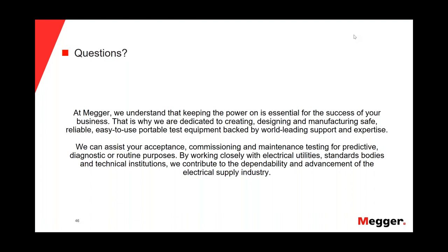All right, thank you. Henning, what is the difference with measuring PD in millivolts instead of picocoulombs? Well, I think that question depends a little bit on which method you're using. If you use a conventional method, you're typically using the PD in picocoulombs. And if you use an unconventional method, then you use millivolts. But if you use the typical standardized method, which follows IEC 60270, then you would measure the apparent charge in picocoulombs.